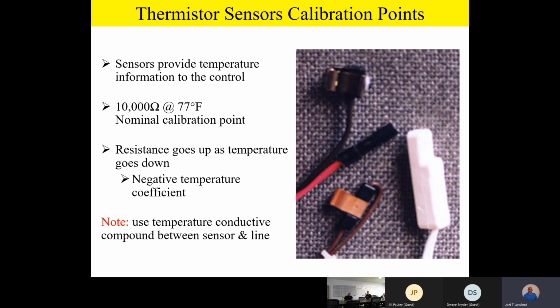I like to put it in saran wrap, and then stick that sensor into water that I know is 77 degrees, and I take my ohm meter, and I set my ohm meter up, and I read the ohms on that sensor. It should read 10,000 ohms or very, very close to it at 77 degrees. And that's the nominal calibration point for all of our sensors on there.